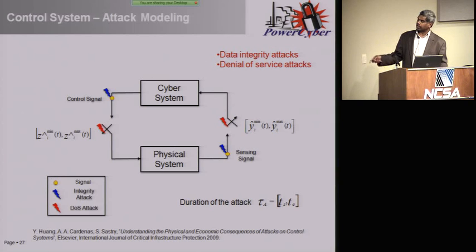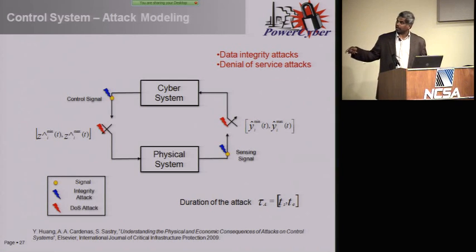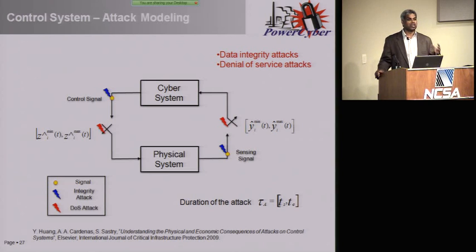When a signal comes from the power system, the operator or the control center logic knows the expected value and acceptable range. The moment the actual value exceeds that range, it becomes suspicious and triggers investigation. But a smart attacker tries to stay within that bound, artificially creating a ramp function or some combination so the data value still complies with the range. It looks legitimate, but it's actually an attack that impacts the physical system.